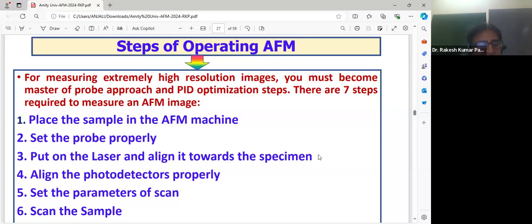Most of the times we make a mistake over here. You are placing the specimen, you are putting the probe there, but if you do not focus the laser beam properly, it becomes very difficult to measure the deflection between the cantilever tip and surface. This third step becomes very important. The focusing should be appropriate. For this focusing, the laser beam that you are using must be very pinpointed, very narrow.